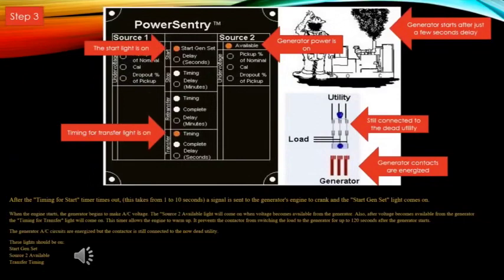Step three: after the timing-for-start timer times out — this takes from one to ten seconds — a signal is sent to the generator's engine to crank, and the gen start light comes on. When the engine starts, the generator begins to make AC voltage. The source two available light will come on when voltage becomes available from the generator. After voltage becomes available from the generator, the timing for transfer light will come on. This timer allows the engine to warm up a bit, allowing oil to get up on the crankshaft so you're not throwing a load on a dry shaft.